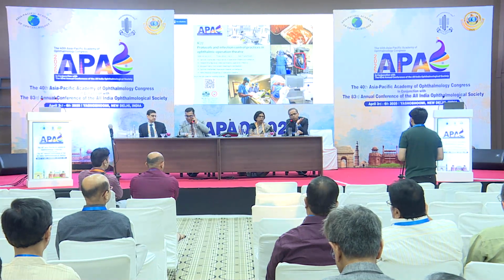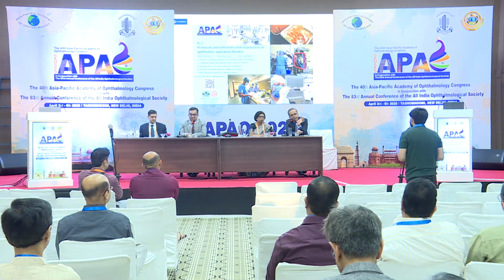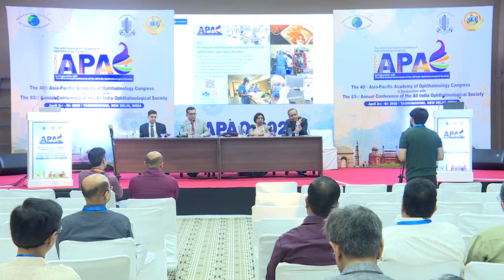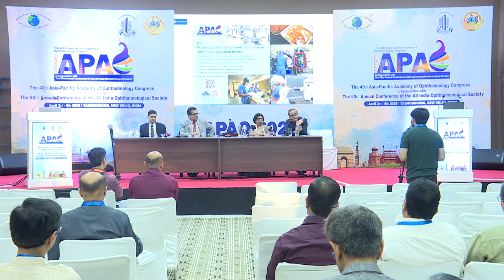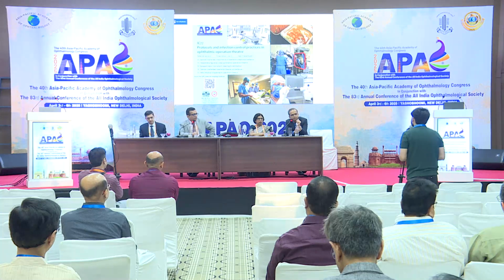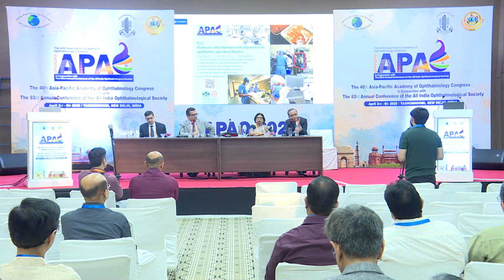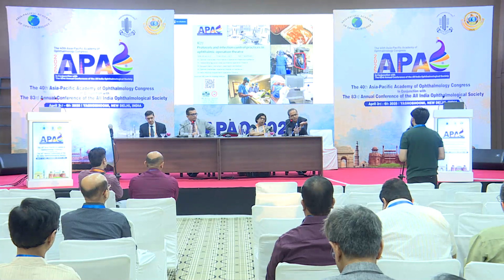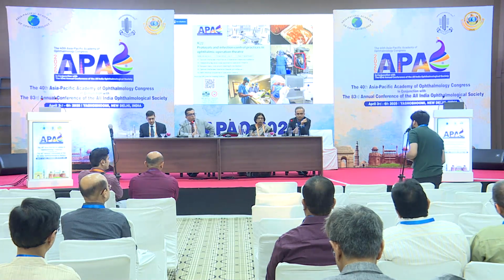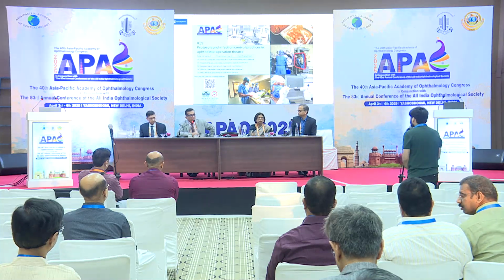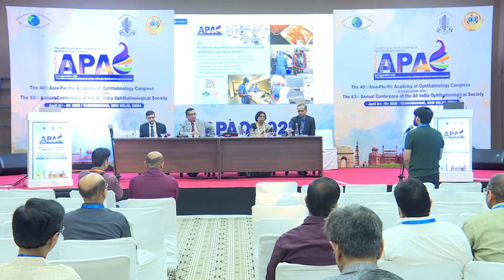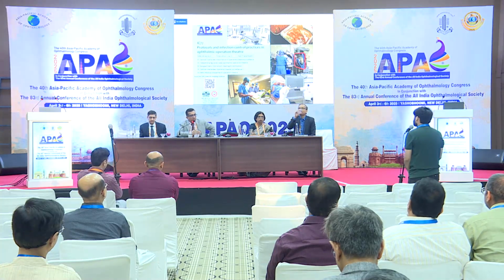I think that will depend more on your load. Basically, the classes are not regarding the autoclave amount that is being done. All autoclaves will sterilize your equipment. Class S basically does not have the pre-vacuum. Yes. Okay, Class B has the pre-vacuum, so what it does is it quickens the time, shortens the time. That is the main purpose of that. So the costlier you go, the more these machines will do all these things better. That is the only thing. Otherwise, any class is fine as long as you are using indicators to confirm. Thank you. So the one that you're using is fine enough if you have a smaller load. Yeah. But if you have fewer packs, then you need to have these flash autoclaves.